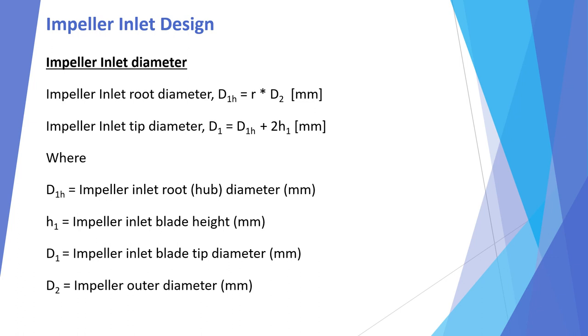For the impeller inlet diameters: the impeller inlet root or hub diameter D1h = r × D2. Since D2 and r are both known, D1h can be calculated. The impeller inlet tip diameter D1 = D1h + 2 × H1, so the inlet tip diameter is also known. Here, D1h is the root or hub diameter, H1 is the impeller inlet blade height in mm, D1 is the impeller inlet blade tip diameter, and D2 is the impeller outlet outer diameter in mm.